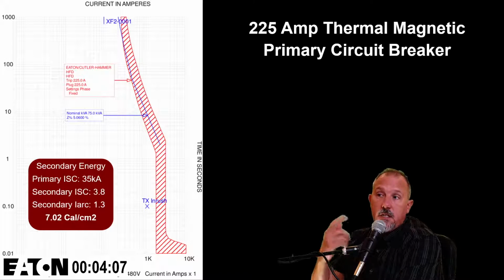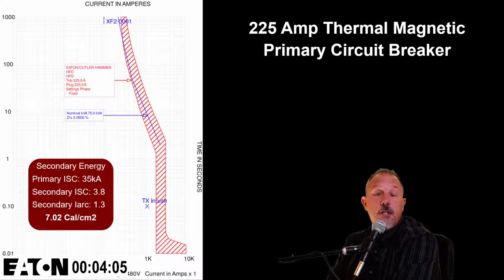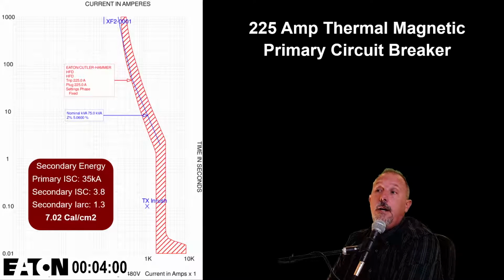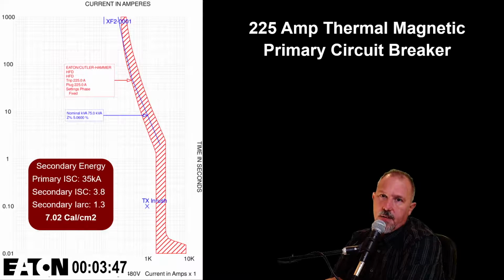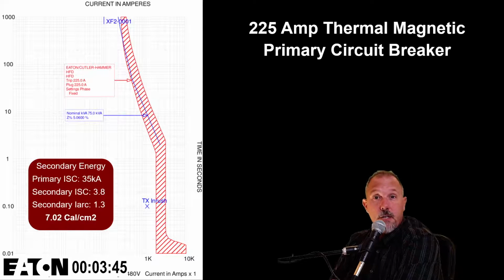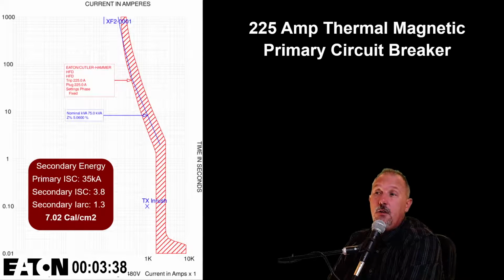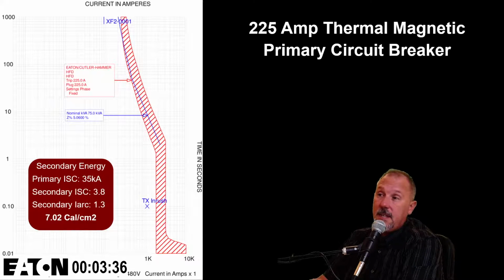You'll notice that this circuit breaker is on a primary, so it's going to provide short circuit protection of the transformer. It does a pretty good job of doing that. Some people might say, well, hey, Tom, you're in that damage curve of the transformer. But again, be mindful that the overload protection is going to come from your secondary main overcurrent protective device, not necessarily from your primary overcurrent protective device. That primary device is going to be there for short circuit internal faults within that transformer. Your overload protection is going to come from the secondary.